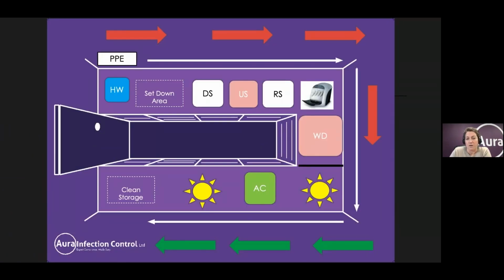So we would then follow our successful sterilization cycle with a second inspection. We want to be making sure that we are not finding any wet pouches when they come out of the autoclave. That if they're pouched after they've gone through the autoclave, they are allowed to cool down and dry effectively, and that we are being mindful of keeping those items sterilized so that they are safe for reuse. We want to make sure that the inspection stage also signs off that any validation that was used has passed before we move them on.